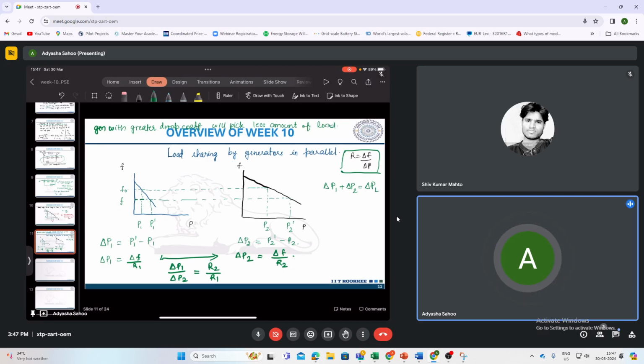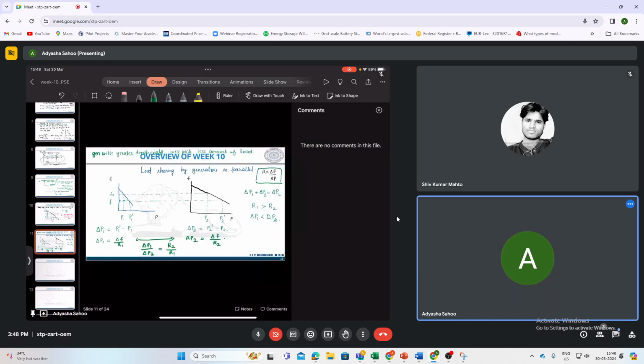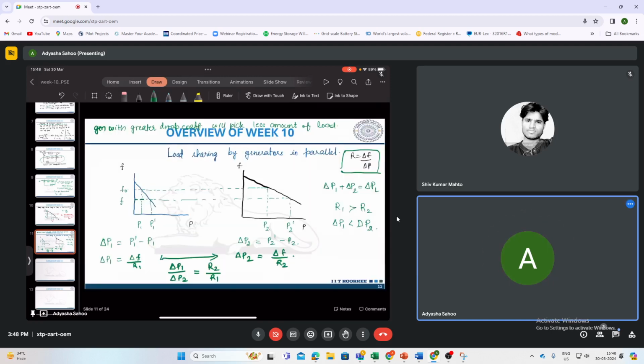That means, firstly, we had remembered the relation between R1 and R2. R1 was greater than R2, which means that the amount of load picked up by generator 2 will be more than generator 1, because here we see it is inversely proportional, right? And that you can see from this diagram also. You see delta P2 looks greater than delta P1.